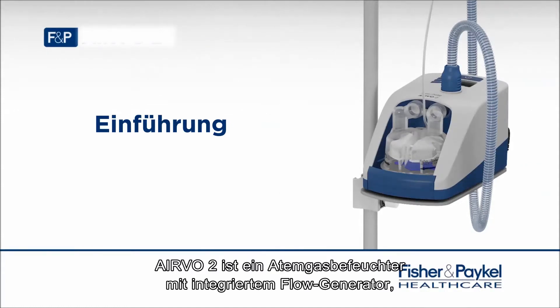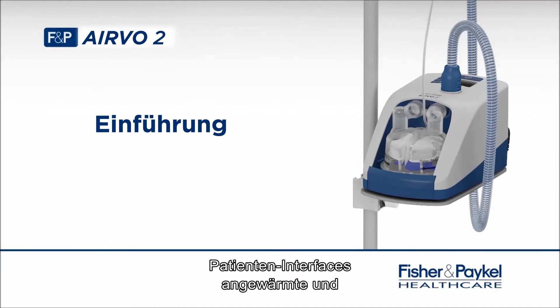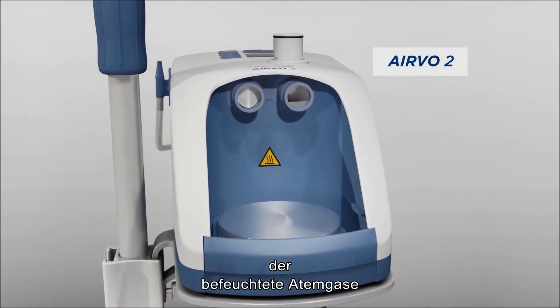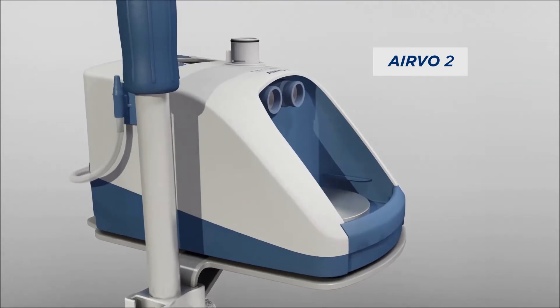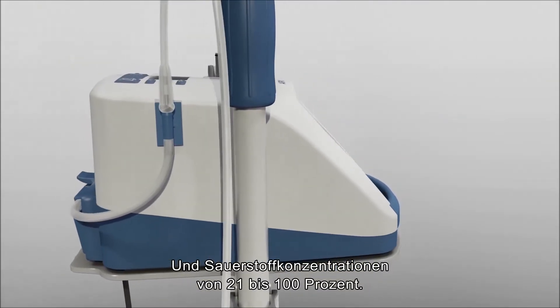The AIRVO 2 is a humidifier with integrated flow generator that can deliver high-flow, warmed and humidified respiratory gases to spontaneously breathing patients through a variety of patient interfaces. The AIRVO 2 humidifier can deliver humidified respiratory gases at flows from 2 to 60 litres per minute and oxygen concentrations from 21 to 100%.